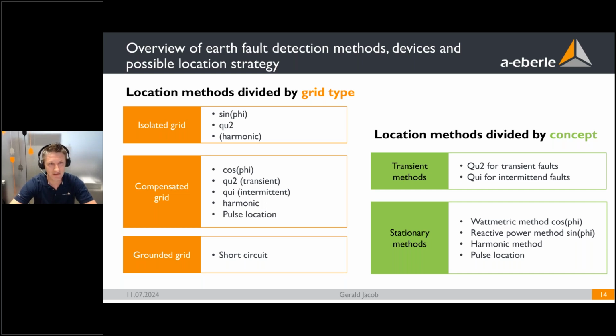In the isolated grid, there are some methods that are quite reliable: the reactive current or reactive power method, sinus phi, and the transient method QU2. In compensated grids, the QU2 transient method can be used as well, and there are some further methods. But in grounded grids, in the end, you can only use the short circuit algorithm, which of course can also be used in isolated and compensated grids.